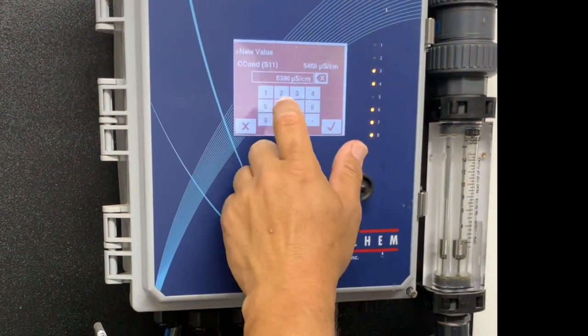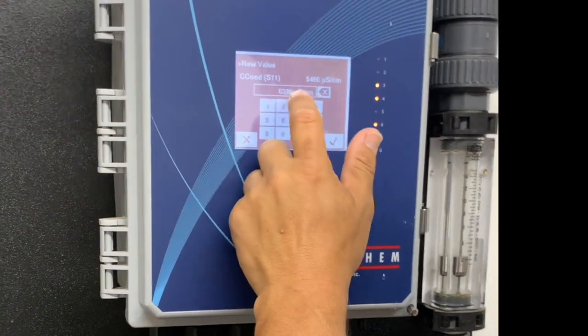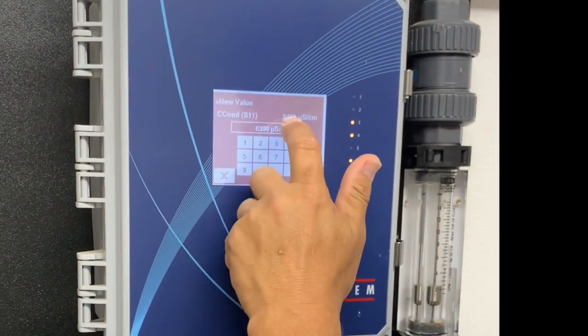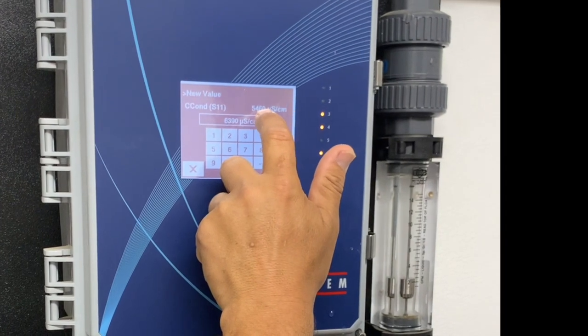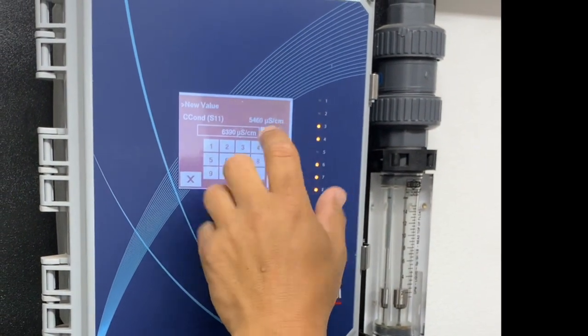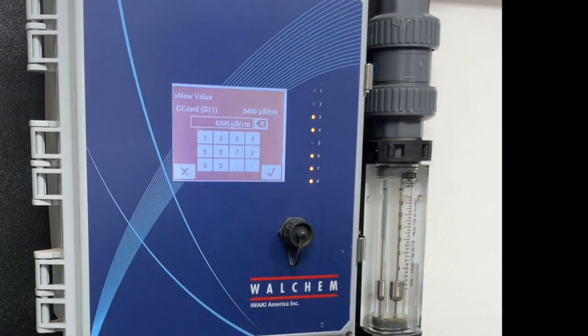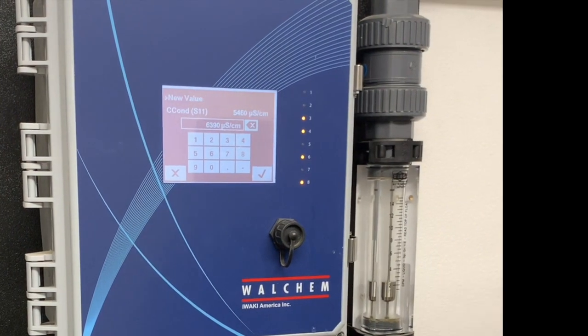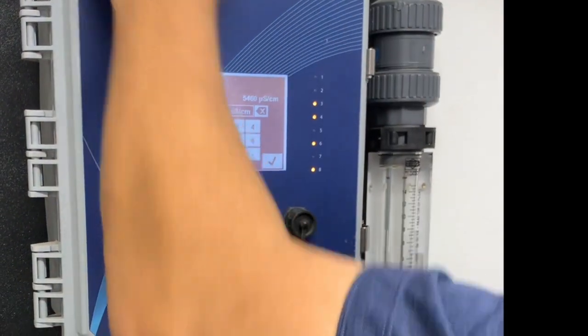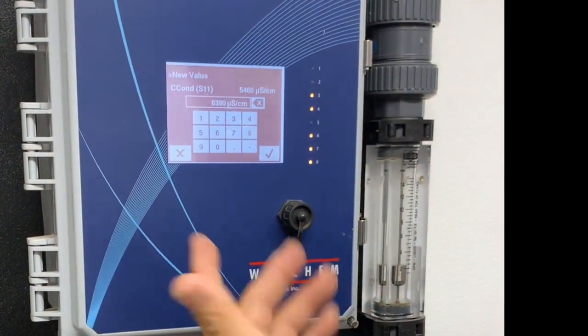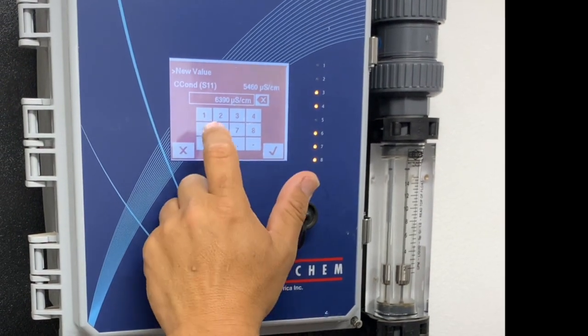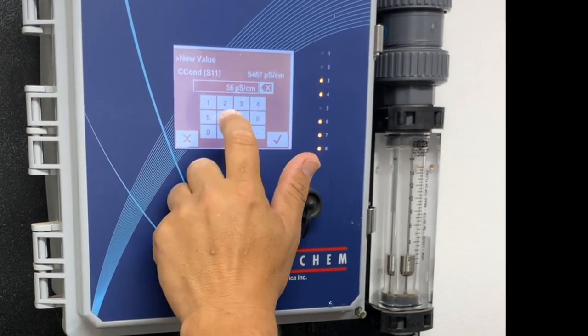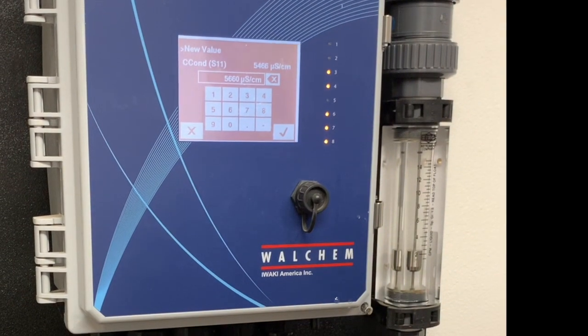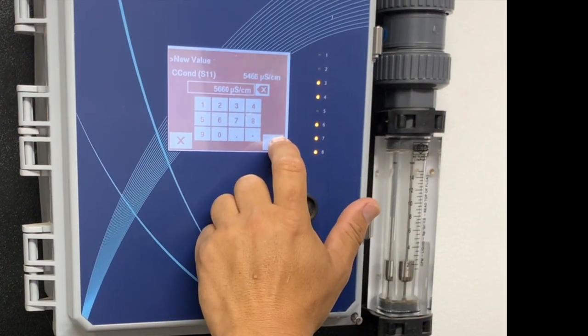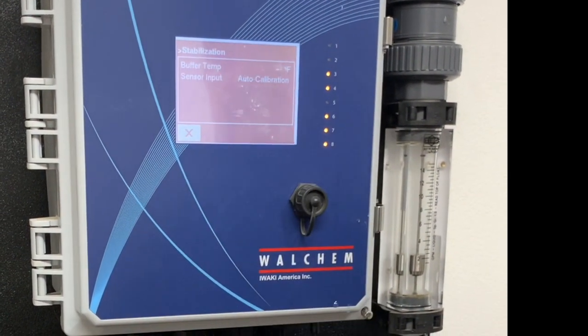This is what the actual default reading is, 6390. This is what the reading for the probe that we have in there now that it's reading. And in our case, off of our handheld, our reading is 5660. So we're just going to go in real simple, 5660, and hit our calibration, our new reading. Hit that.